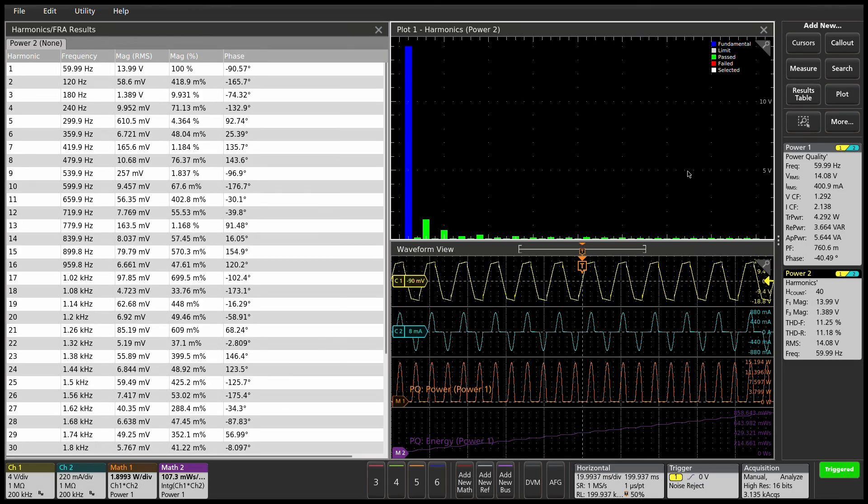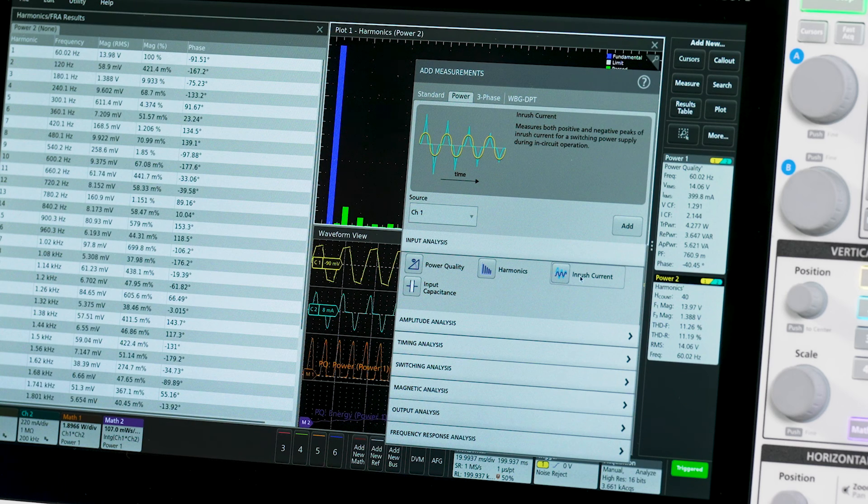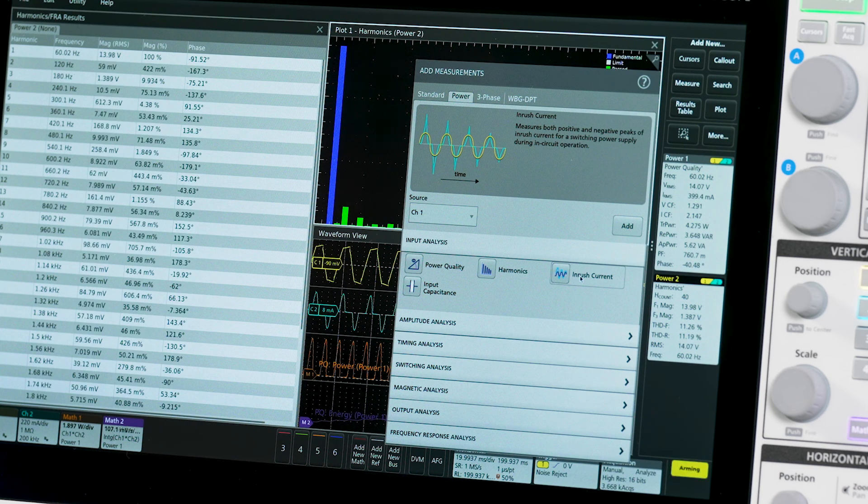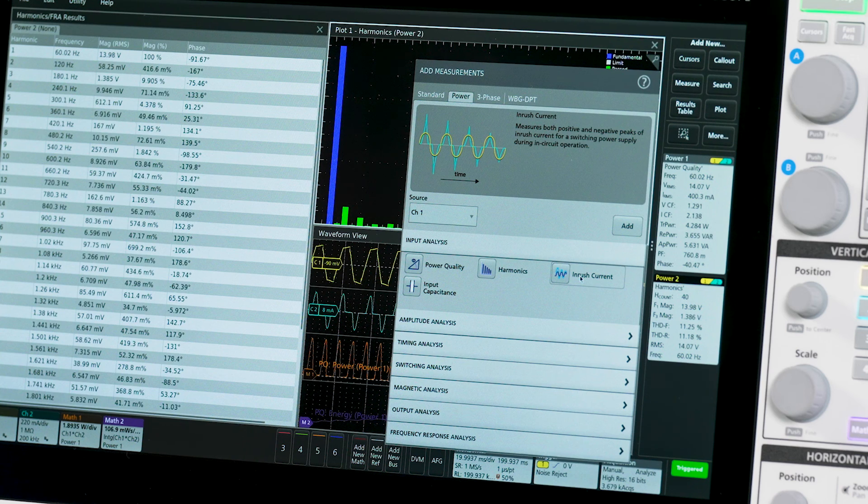The instantaneous inrush current is often measured to verify that a power supply's input capacitors charging current does not exceed the maximum current rating for the capacitor or any other components in the input path.